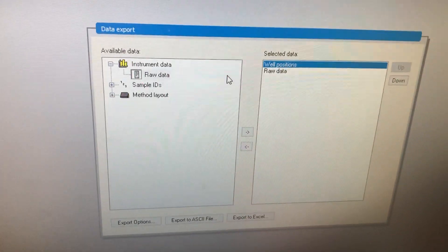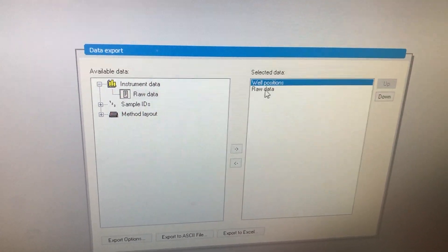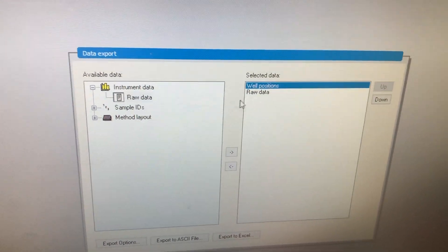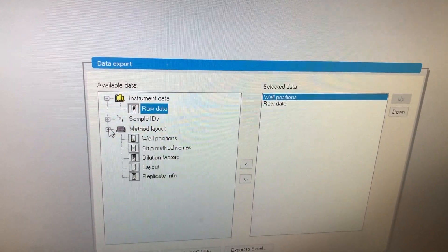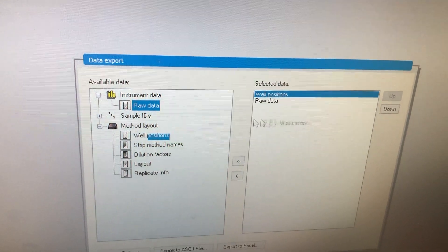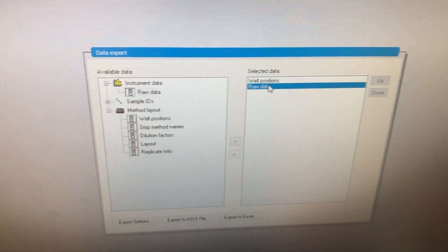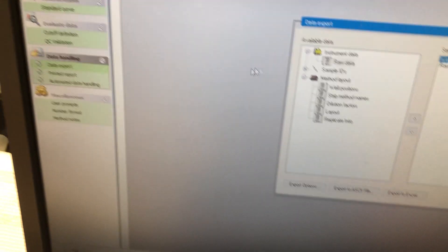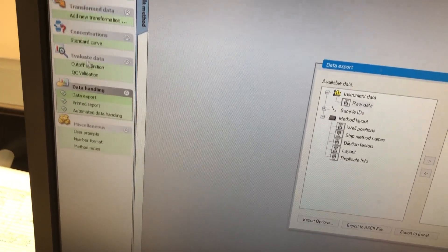Along the lines of analysis, your options there ought to be data export options. And this is a little bit clunky here, but as long as it's splitting out the raw data, I like to have it spit out the well positions as well. Just again, this is just drag and drop. But I just like to have it show me the well positions to make sure that I'm seeing the data in the way that I think I'm seeing the data and then just have it spit out the raw data. And that's what it'll do when it exports. This might be important to check that occasionally. And the rest of the options here, I typically leave default. And we can just go to Next.